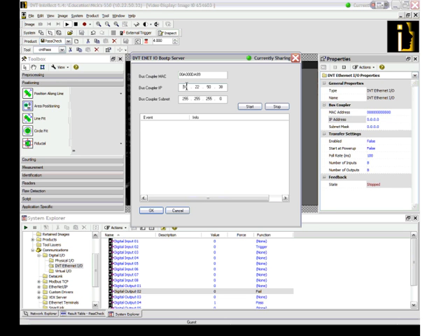So there you have it. I have my MAC address in, IP address, my subnet mask in. I'll click on Start, and you'll see this event labeled Start and info saying listening for BootP request. This is basically telling me that it is now listening for that Ethernet I/O module to boot up with this MAC address so it can send this configuration that I have here.